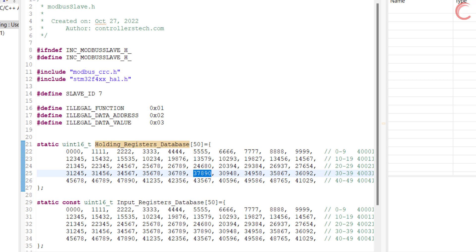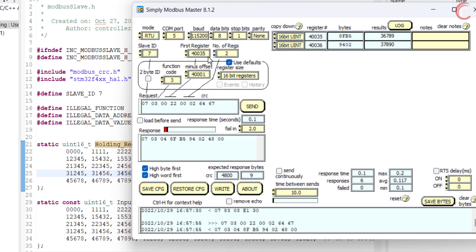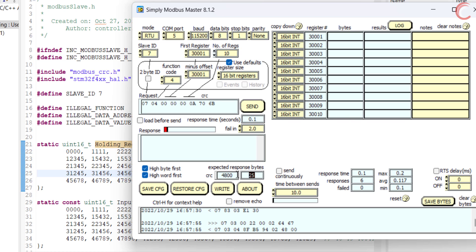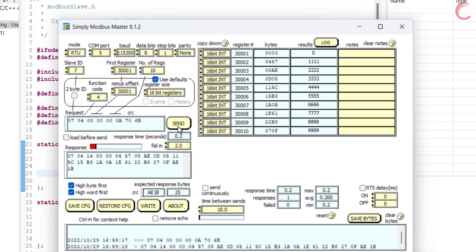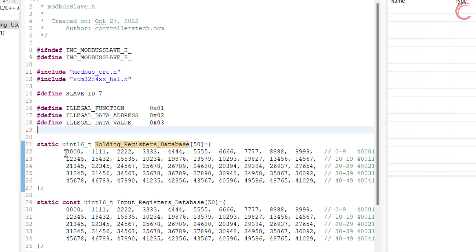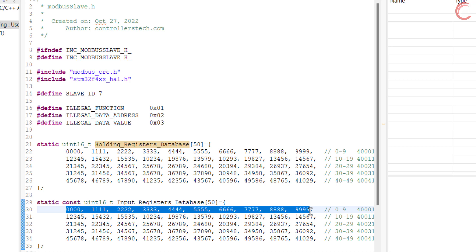Now let's quickly see function code 4 to read the input registers. Let's say the master wants to read 10 registers starting from 30001. Here you can see the master is expecting 25 bytes in total. It has received all 25 bytes, and you can see the values for the respective registers. These are the 10 values the master has received, and they are exactly the same as what we have stored in the database.